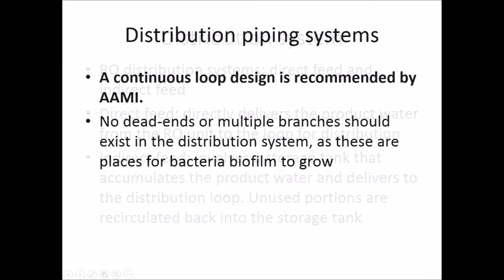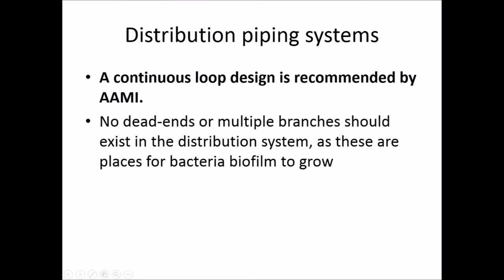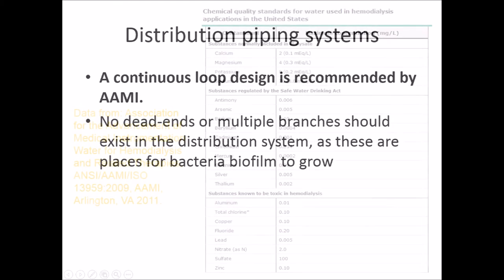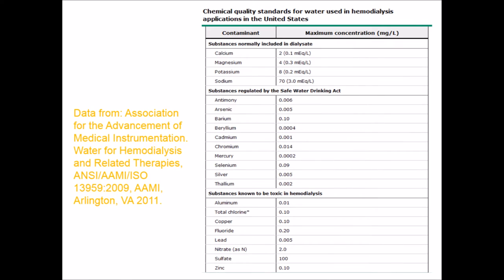The standard is a continuous loop design, recommended by AAMI, with no dead ends or multiple branches in the distribution system, as these are places where bacterial biofilm can grow. Regarding chemical quality standards of water used in dialysis applications in the US, there are a number of substances toxic to the patient with maximum permissible levels. Chemical quality should be tested at least once every six months.